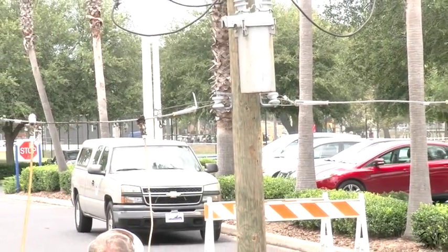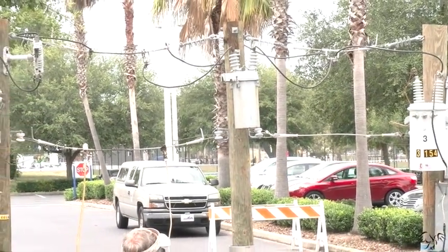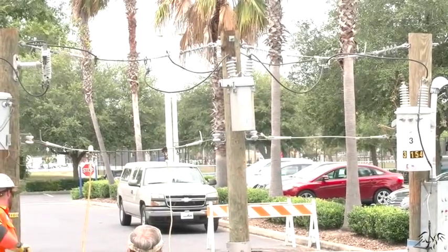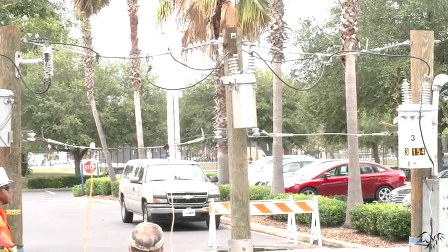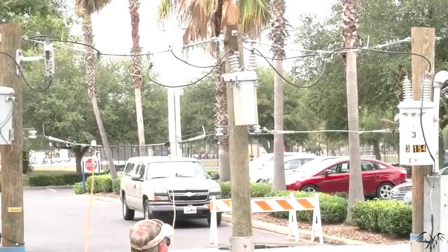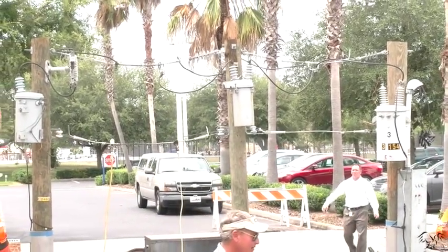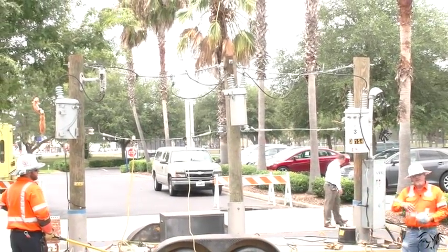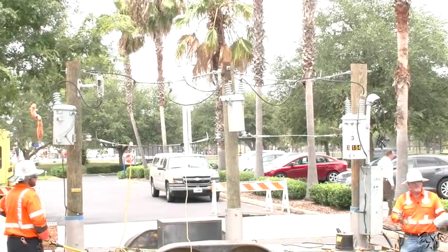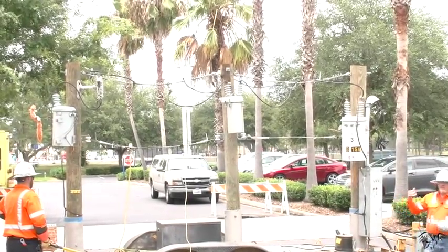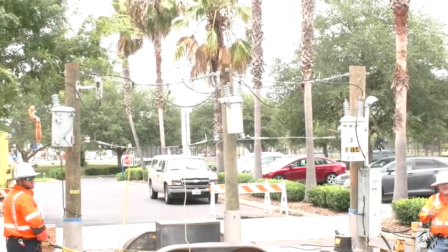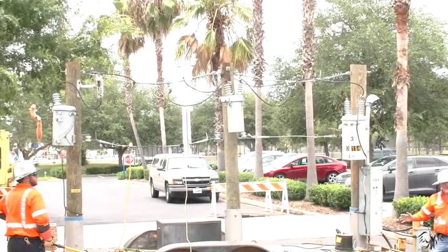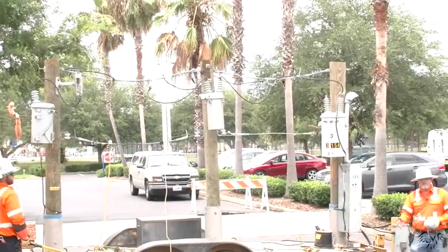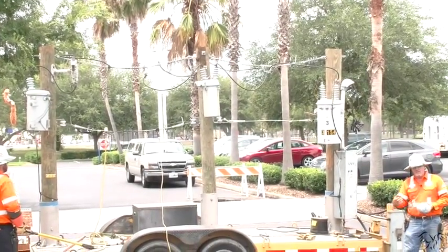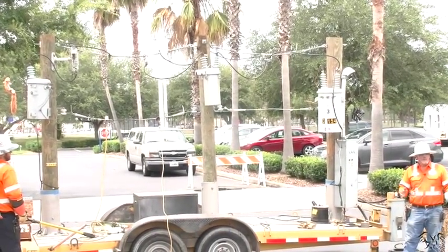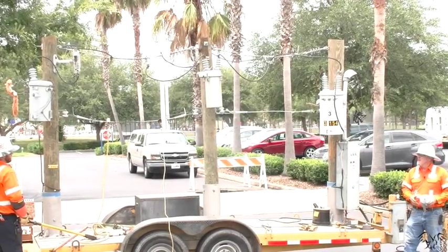Have you guys ever been at home at night and your lights go out, then come back on, then go out and come back on? That's a breaker operating, designed to do it 3 times. If you count, on the 3rd time it's not coming back on. If it comes back on the 2nd time and stays on, chances are it'll stay on. It's designed so that if a tree falls and hits the line, the breaker opens and kills the power long enough for the problem to clear itself. It'll close back in, power's restored, and nobody even has to come out.